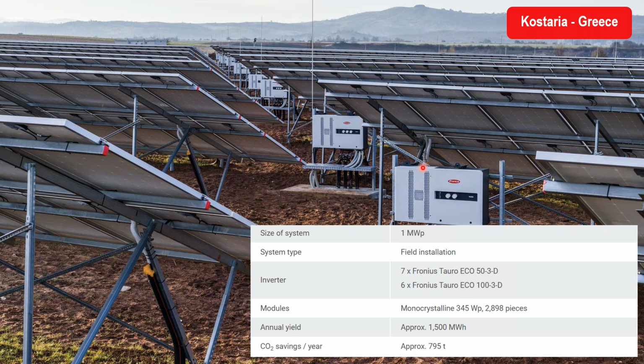The direct version, as you can see here, is an inverter that you can connect the string cables directly to. We also have 6 Fronius Tauro ECO 100, also direct version. That brings a total of just about 1.01 megawatt. In terms of the number of modules, we are talking about 2,898 pieces of 345 watt peak. The annual yield in this installation is approximately 1,500 megawatt hours. As this installation was done in late 2018, we have already gathered a lot of useful information about the Tauro. Once we start selling this inverter into the market, we are very sure that it is going to be extremely successful.